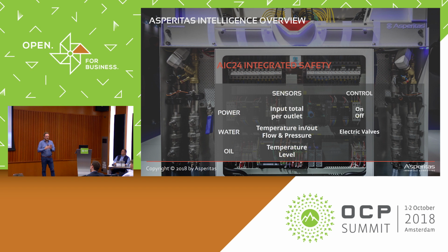One of the features of this system is that we can optimize the water circuit. We can optimize for high return temperatures, maintaining a constant delta of approximately 10 degrees C, but we can modify that accordingly, or let it be passive with just a constant flow rate.